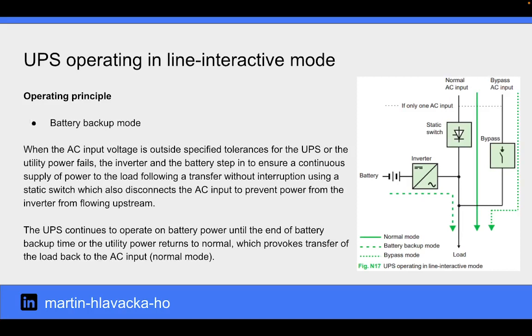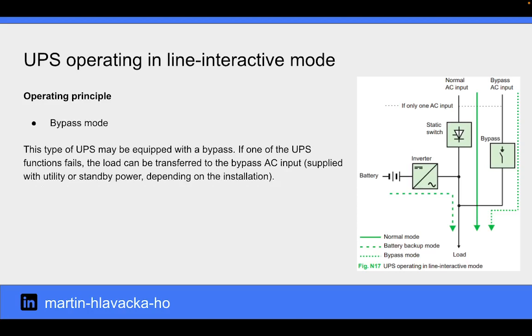In battery backup mode, the inverter and the battery step in to ensure a continuous supply of power to the load, following a transfer without interruption using a static switch that also disconnects the AC input to prevent power from the inverter from flowing upstream. This type of UPS may be equipped with a bypass. If one of the UPS functions fails, the load can be transferred to the bypass AC input.